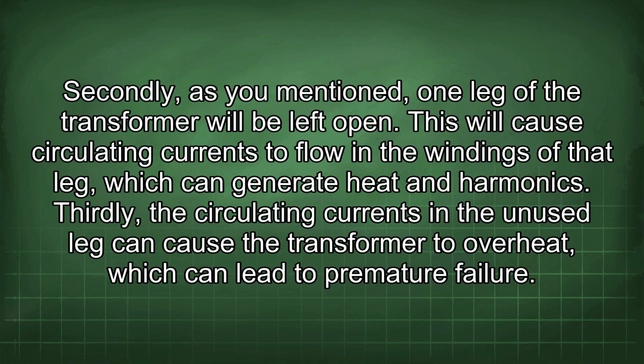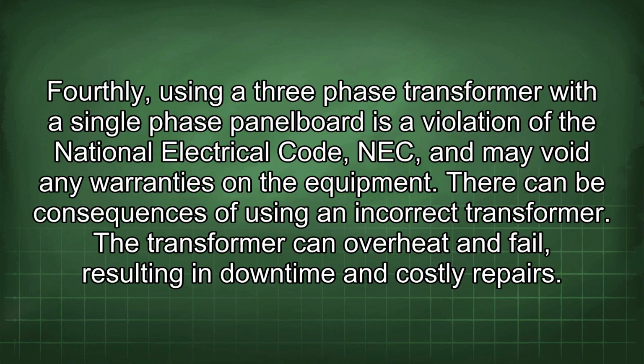This will cause circulating currents to flow in the windings of that leg, which can generate heat and harmonics. Thirdly, the circulating currents in the unused leg can cause the transformer to overheat, which can lead to premature failure. Fourthly, using a three-phase transformer with a single-phase panel board is a violation of the National Electrical Code, NEC, and may void any warranties on the equipment.